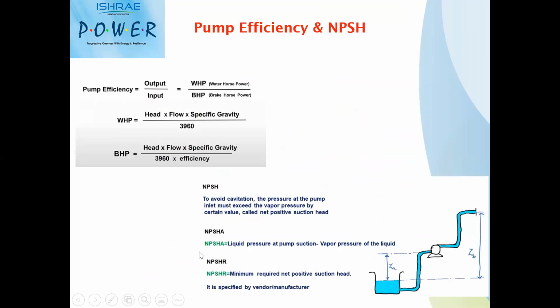So when it comes to NPSH-A, that is what is available at the site. Whenever we are installing a pump in a particular HVAC scheme or any other general pump application, we should know what is the suction pressure available at the suction of the pump based on our installation layout. In HVAC, the primary pumps or the secondary pumps are in a closed loop system where we are pressurizing the complete closed loop system to have the minimum pressure required by the system. So if you physically measure the suction side of the primary pump or the secondary pump, the pressure available due to the pressurized system is called NPSH available.